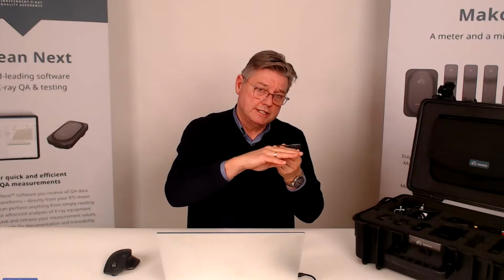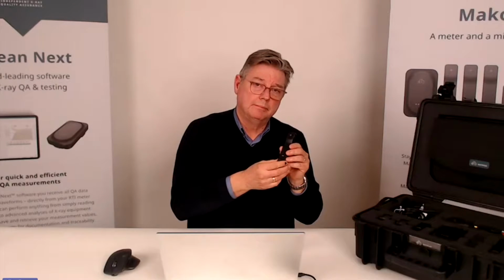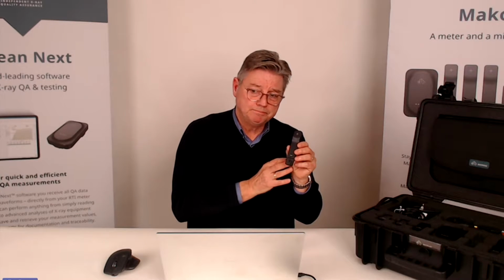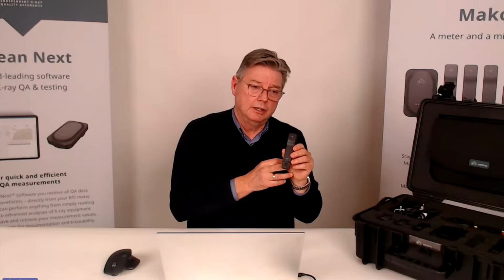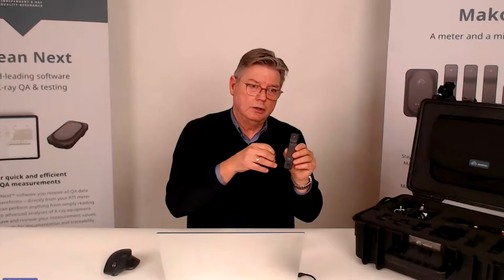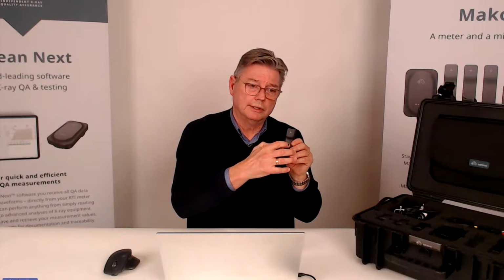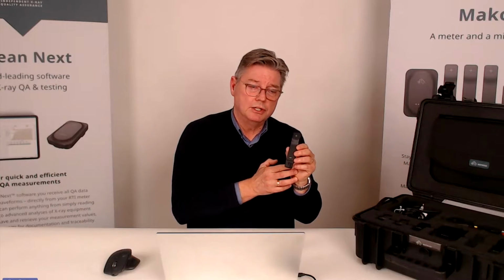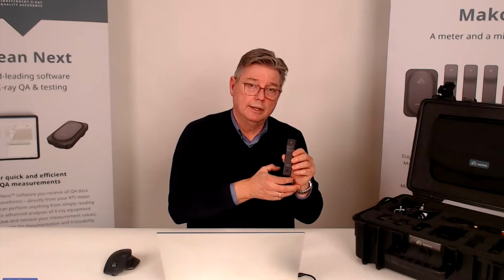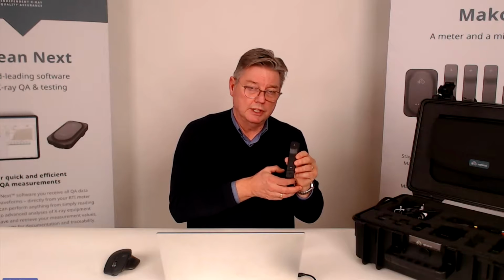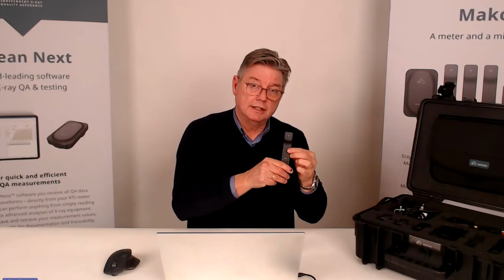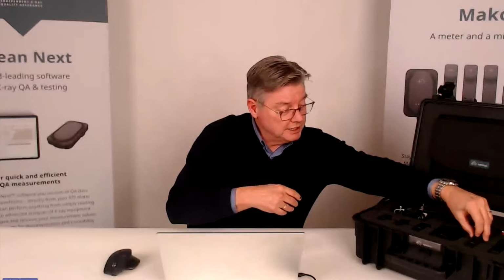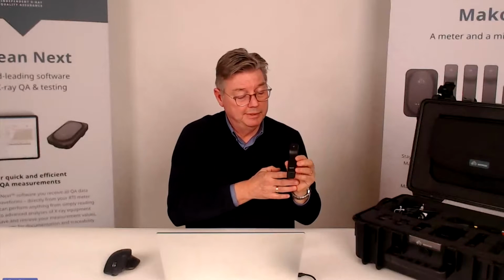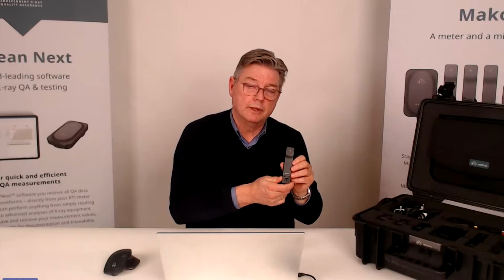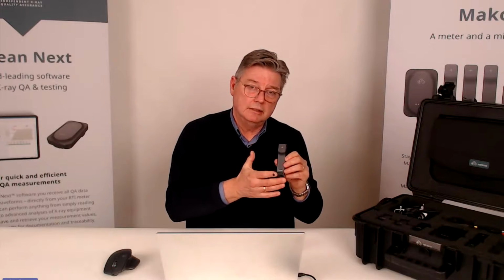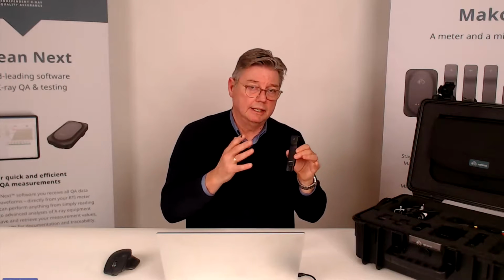So not only is the detector stacked, the diodes are also segmented in each diode, which gives a number of benefits. A few of those we'll look at in a while, but it also provides the algorithms with even more ways to analyze the data and the radiation and provide a solid and high accuracy measurement from this. So that's something which is quite impressive. So that's the RF probe. There is a second probe, which is the Mako probe, and as the name indicates, it's dedicated for mammography measurements. It covers the full range from 18 to 49 kV, without any fuss, without adding any filters or anything like that.